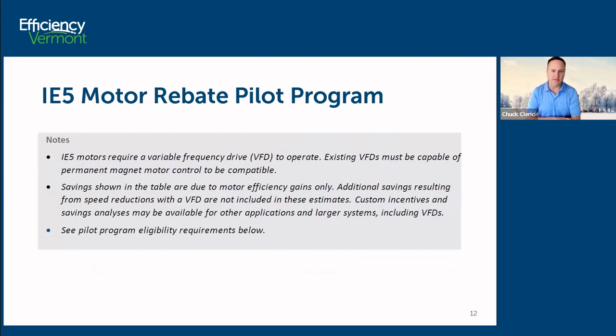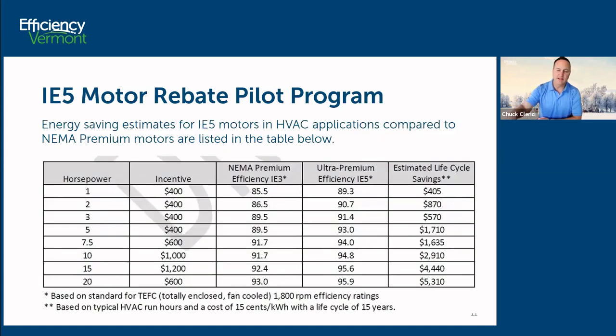The more you slow them down, and they all are required to be on drives, so they will be in a position to be able to modulate, and they'll be operating at part load efficiency, they actually gain even more savings. So eventually the savings in this right-hand column should be significantly more when we graduate this to a full-blown prescriptive program, because we will be taking advantage of the part load efficiency.